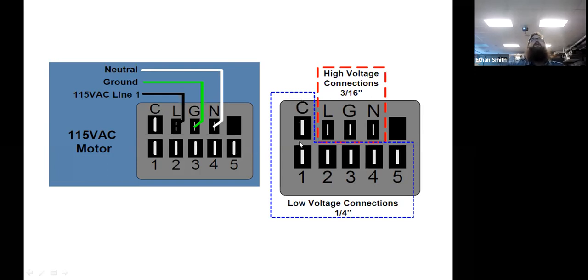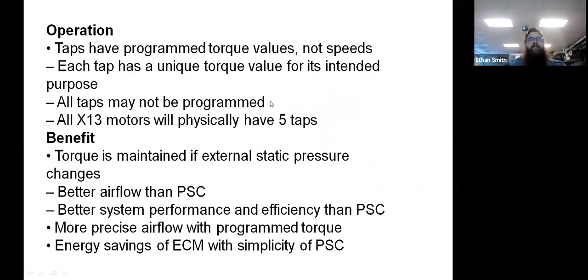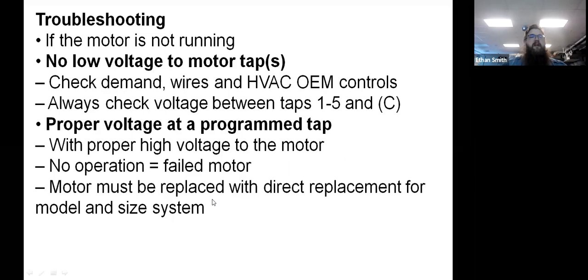So these are your low voltage connections here. And these are your high voltage connections. You'll notice that the high voltage connections actually have smaller spade terminals on these ones that have plugs so that you don't get them confused. Okay. All of the X13 motors will physically have 5 taps, but they can be programmed for up to 9 speeds. We'll talk about how that's achieved. We already talked about the benefits a little bit.